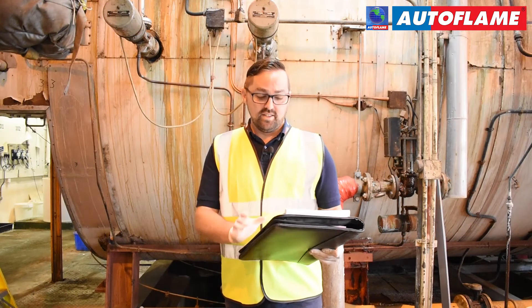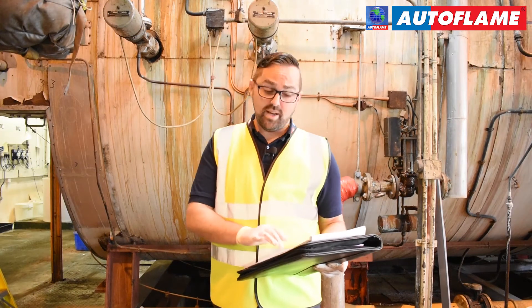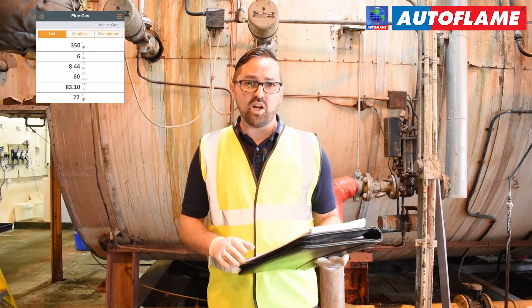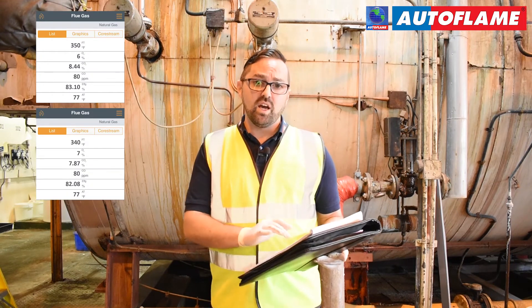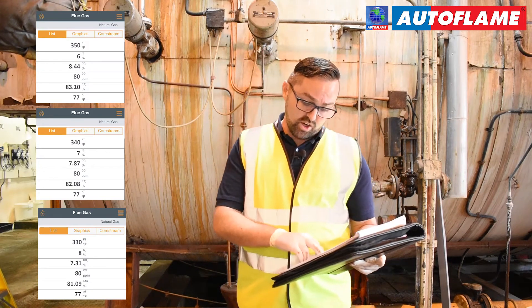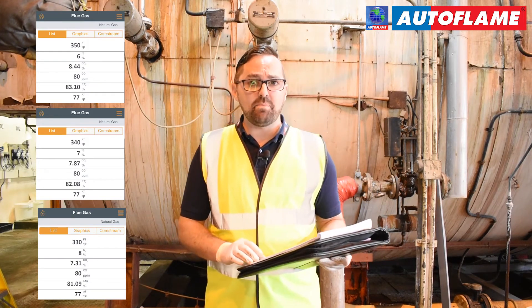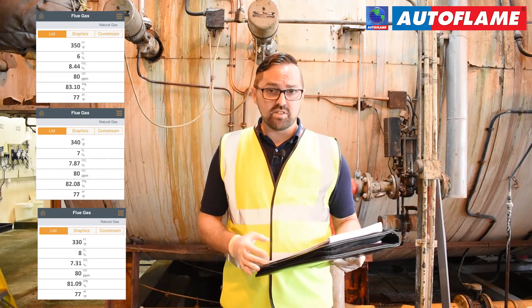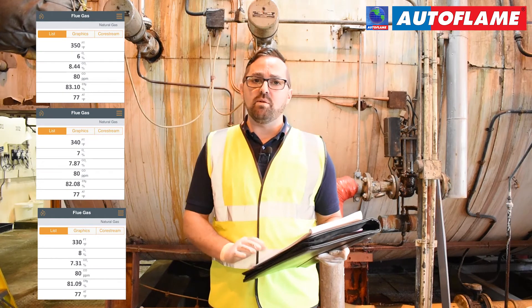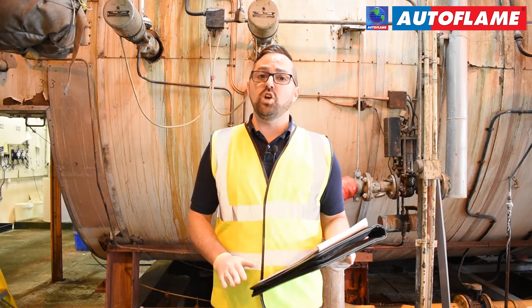Hey guys, readings are as follows. At high fire we were 6% O2, mid fire we were 7% O2, and low fire 8% O2. Across the firing range, the CO is 80 ppm and the NOx is 50 ppm. So real good savings to be made here. It'll be really interesting to see what our emissions calculator has to say. Over to you guys.